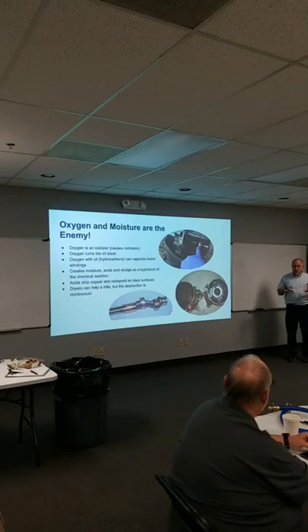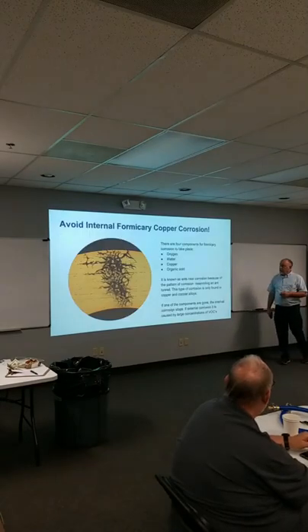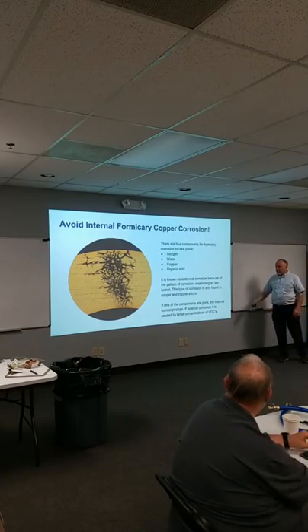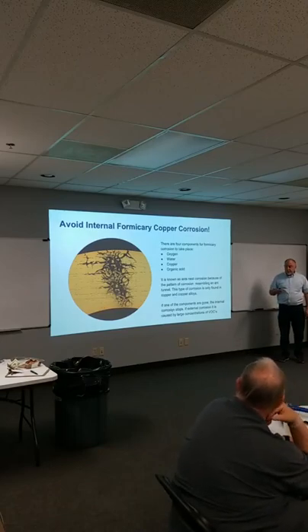The more moisture you have, the more oxygen you have, the more chemical reactions you have, the more problems you're gonna have, right? This is the big one we're hearing today. Oh, these new evaporator coils suck, they all leak, and you have guys taking tons of them back. Well, guess what? It's called formicary corrosion. It takes place when you have oxygen, water, copper, and organic acid, okay? This actually happens from inside or outside of the system. So these crappy evacuations we're doing, that's what's causing this.